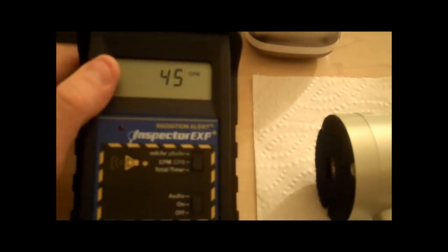Notice our calibration factor is displayed at 169. We're still at the wrong counts per minute. So we're going to scan pretty high. We should be getting about 30 to 40, somewhere in there. We're going to be scanning pretty high here, and the reason is because counts per minute are well off because of the calibration factor.